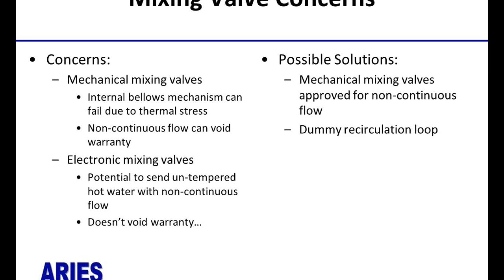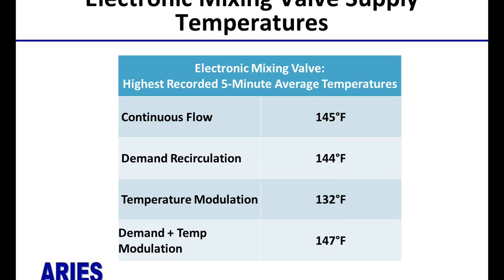But there's ways to address this. There's several manufacturers that produce mixing valves that are approved for non-continuous flow. And there's also this idea of a dummy recirculation loop, which we haven't tried yet. But the idea would be to take a very small pump and install a small recirculation loop that runs just in the boiler room, doesn't incur much of an energy penalty, but allows the valve to see continuous flow.